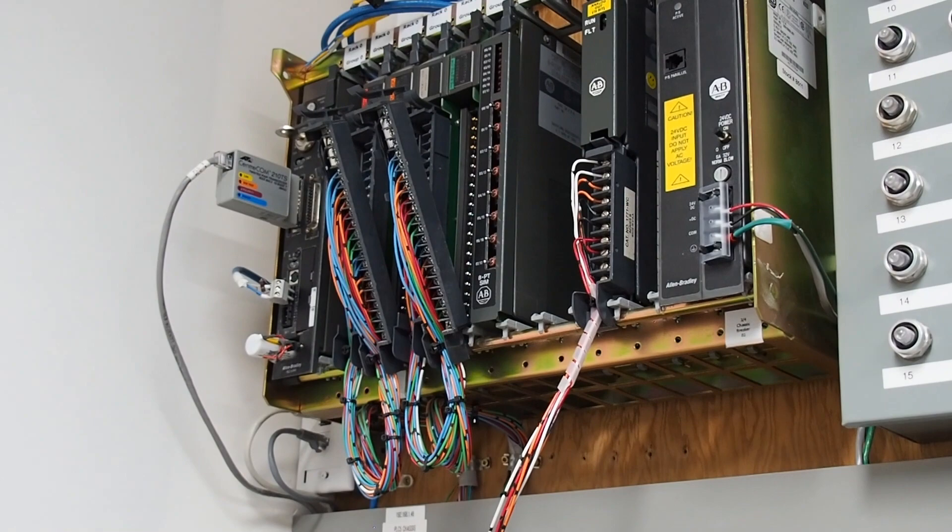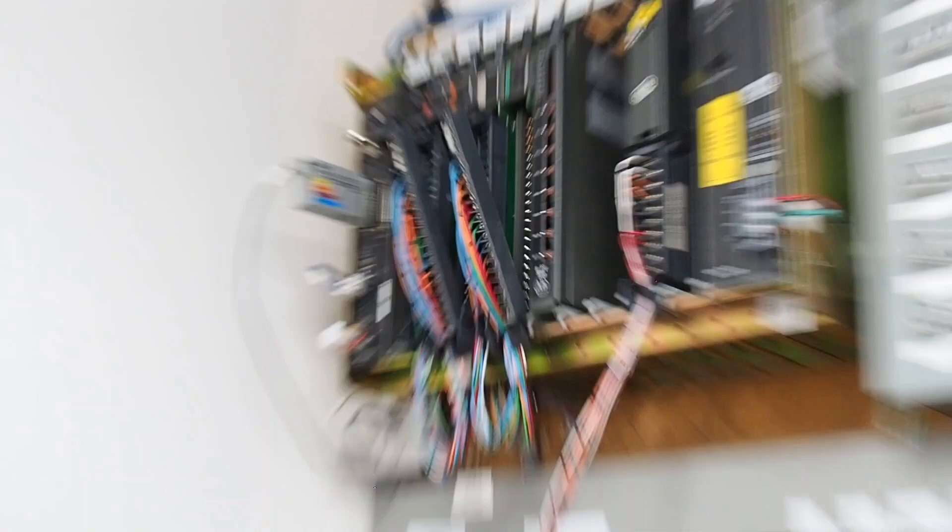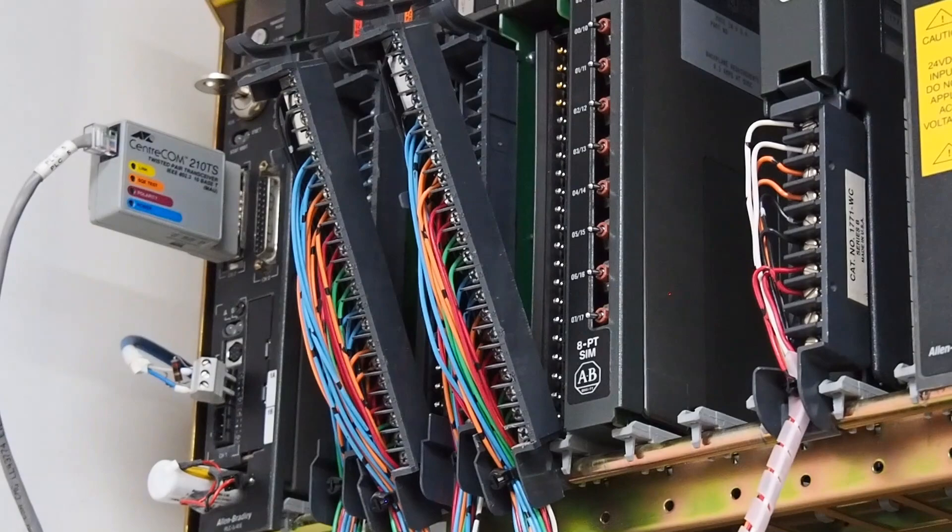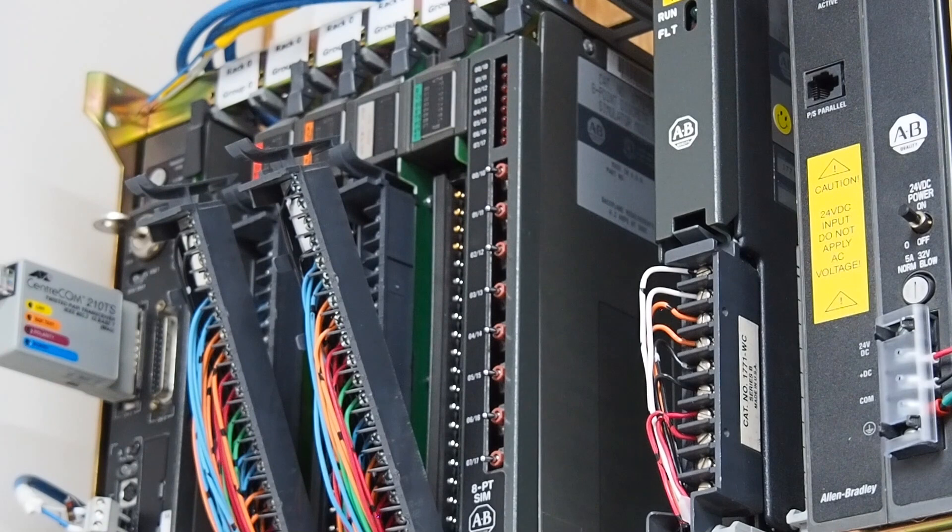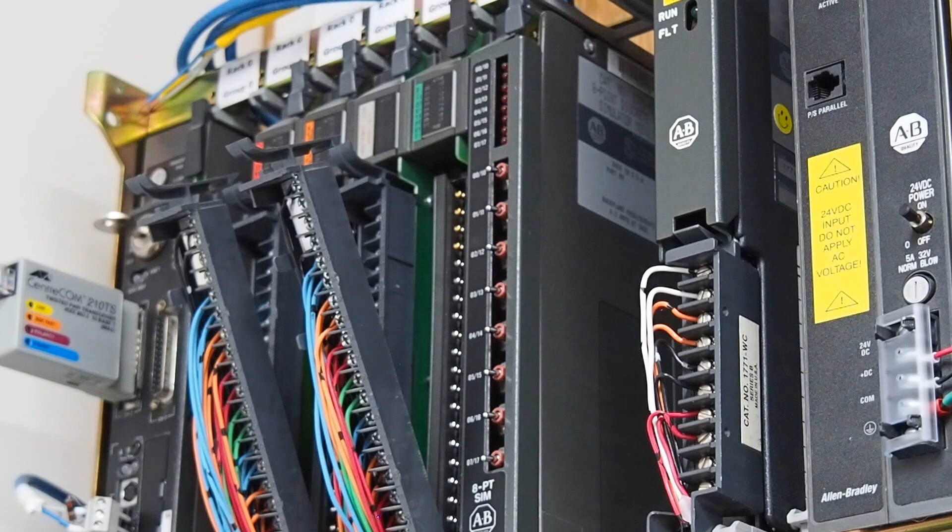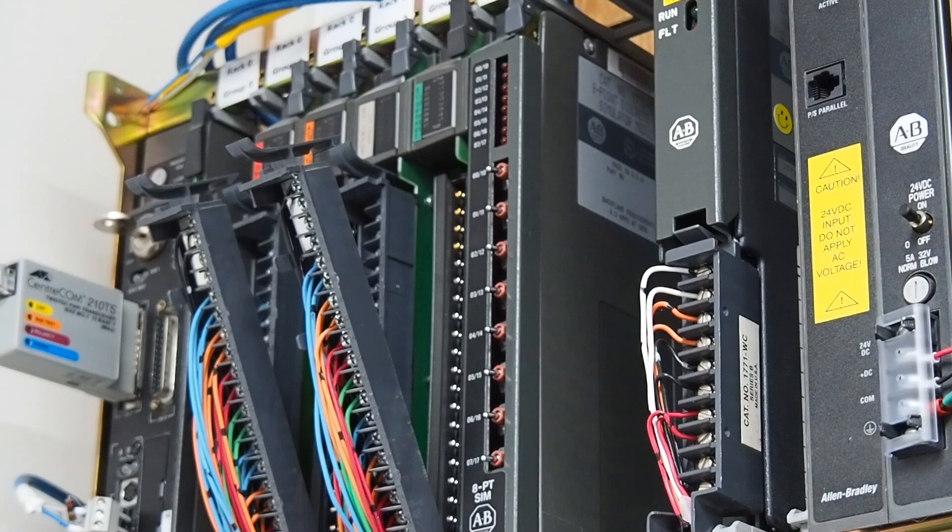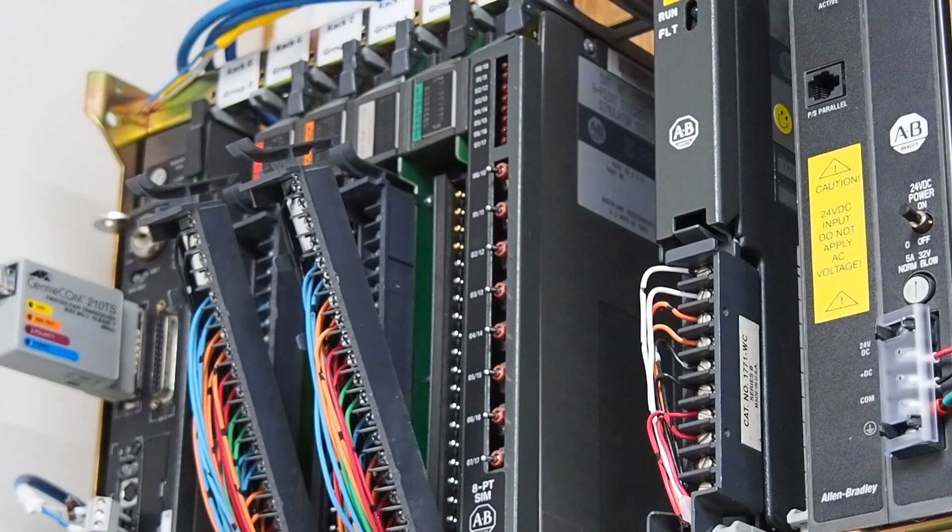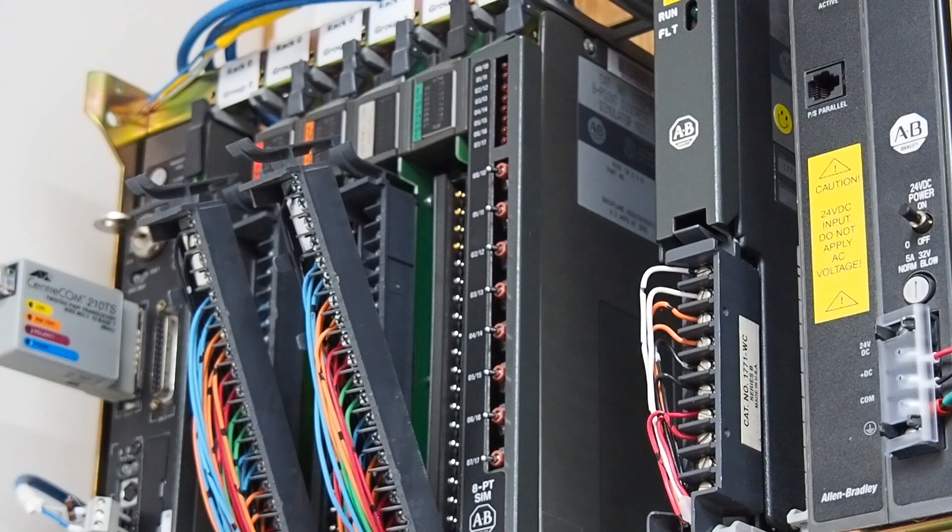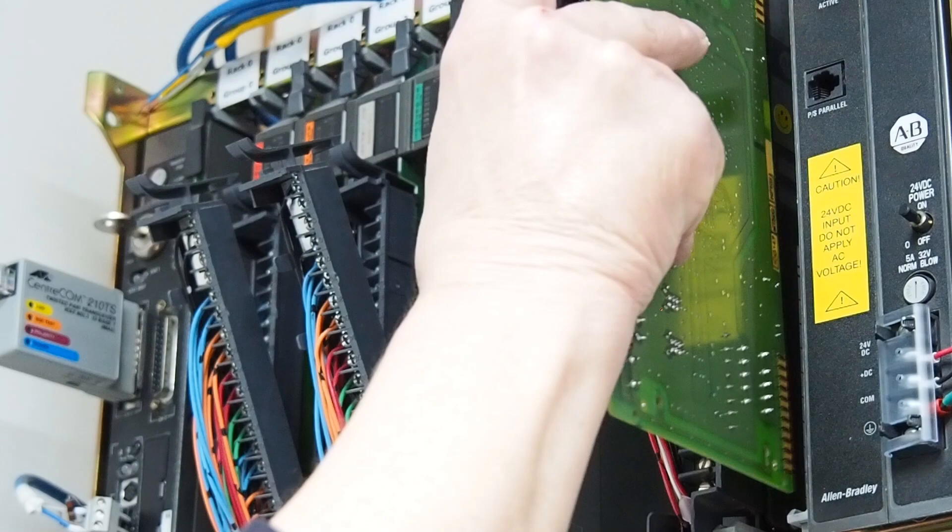Here's our chassis. Right now, it is off. The power is off to the chassis. With PLC5, unfortunately, compared to the ControlLogix or some of the other processors, you're better off to have your chassis powered down rather than powered up, because you can cause damage to the card sometimes. It doesn't always happen. 99% of the time it works fine. I'm going to leave the covers off, which you can do with these. Slide it into the chassis. Set her in tight. Wiring arm goes on.